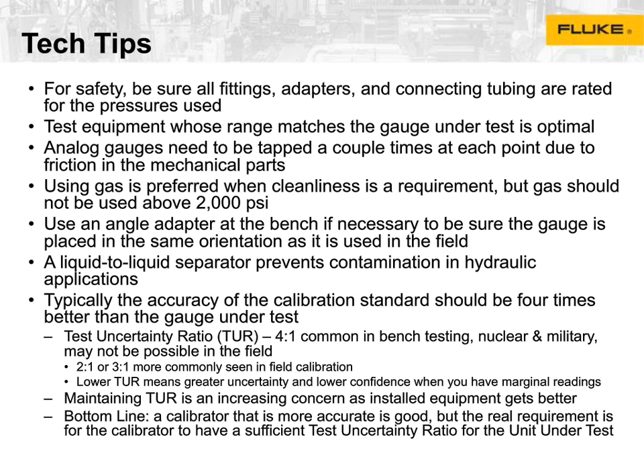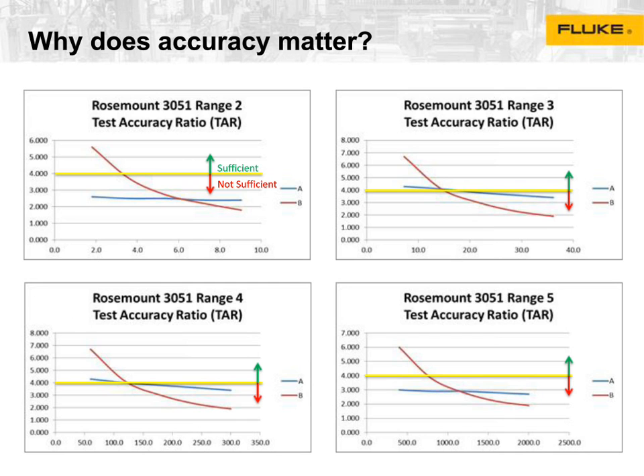Accuracy is, so I've got this bottom line here. Accuracy is a good thing, but the real thing that you need is sufficient test uncertainty ratio. And so let's look at a practical example. I'm going to bring up this graph. This is a little hard to read, but what you're looking at are the 4 test ranges of a Rosemount 3051. You are looking at 2 calibrators made by 2 different manufacturers, A and B.